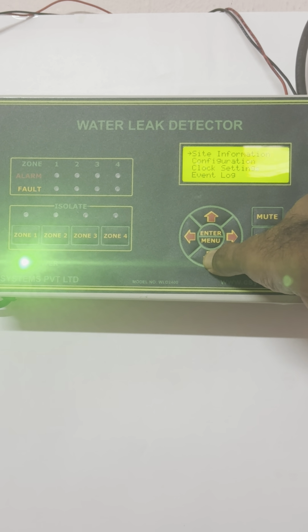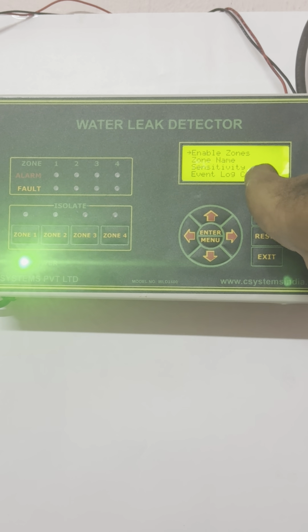So next is the configuration. Go to configuration: enable zones, zone name, sensitivity, and event log clear. How many zones we are going to enable is dependent on the number of sensor cables you have purchased or you are going to install in your facilities. In our case, I have used only one sensor cable, but for demonstration purposes, I will enable two zones to show how the fault works, and the same can be seen in the BMS or the third party integration software.